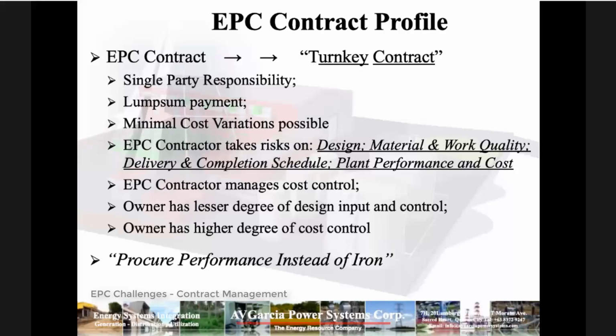Okay? Now, the bottom line is procure the performance instead of the equipment. Anong ibig sabihin nito? Pag bumili ka kasi ng switchgear, pag-deliver ka ng switchgear, basta ni-specify ng client, 13 kV, 630 amps, 2,000 amp bus, etc. Pag nagkamali si procurement of your client and will not specify the withstand of the bus, you can give him the lowest withstand capability.